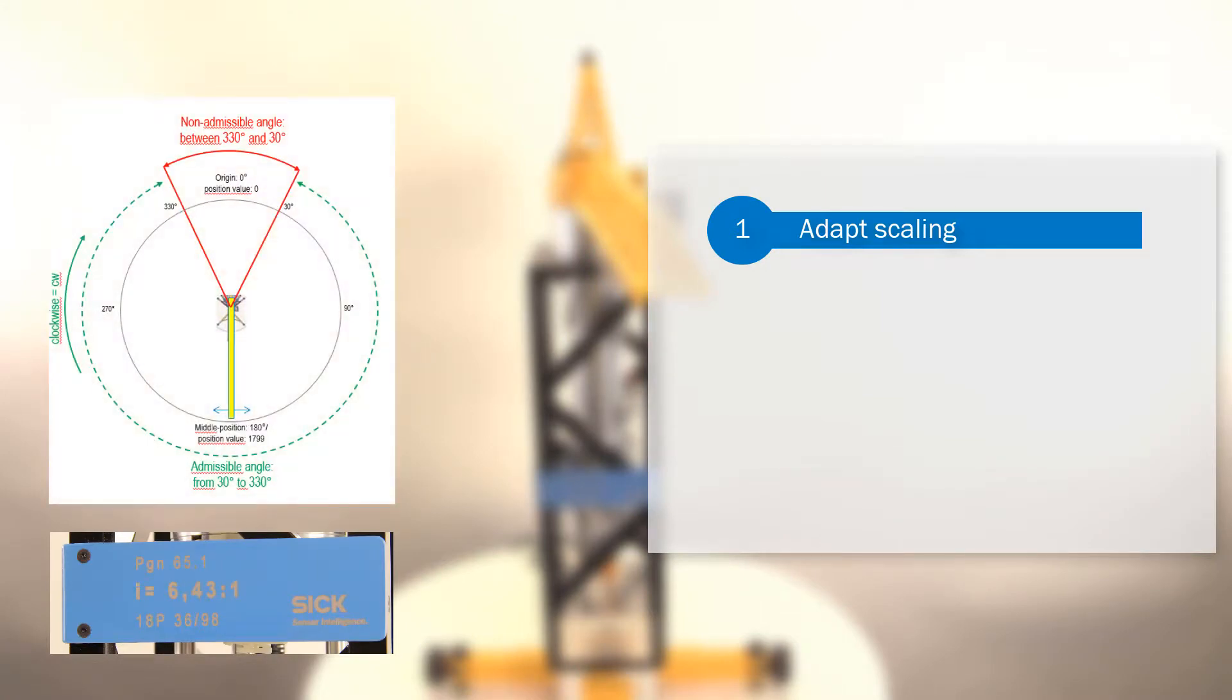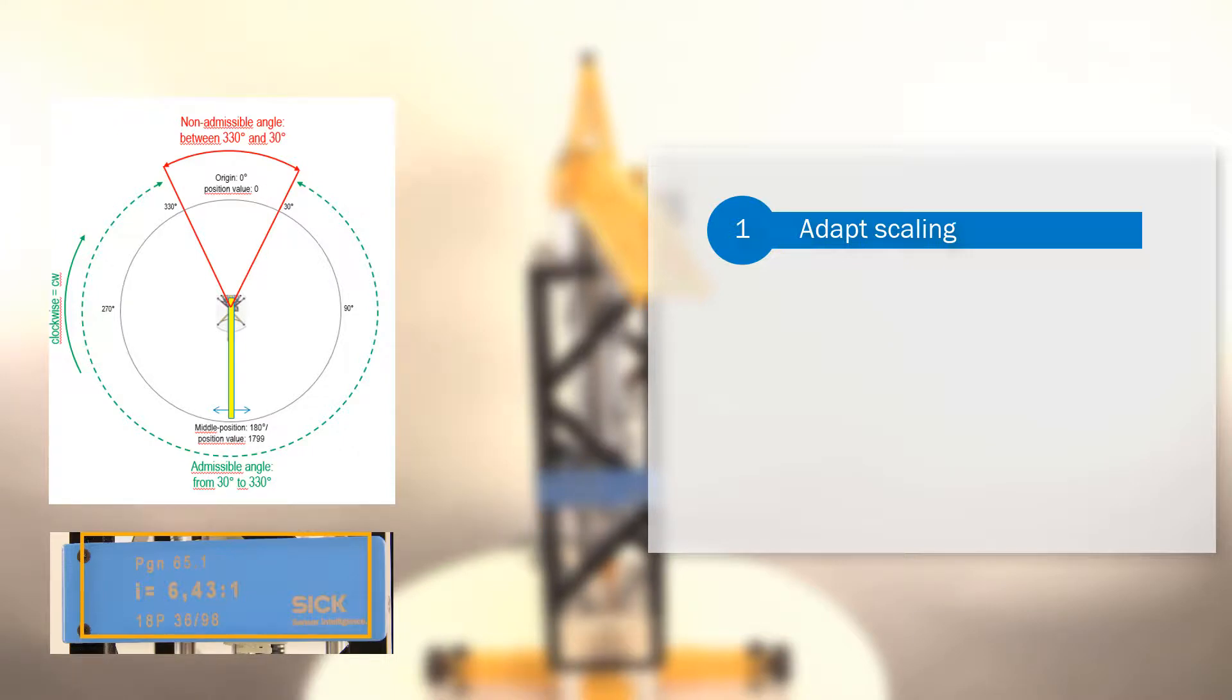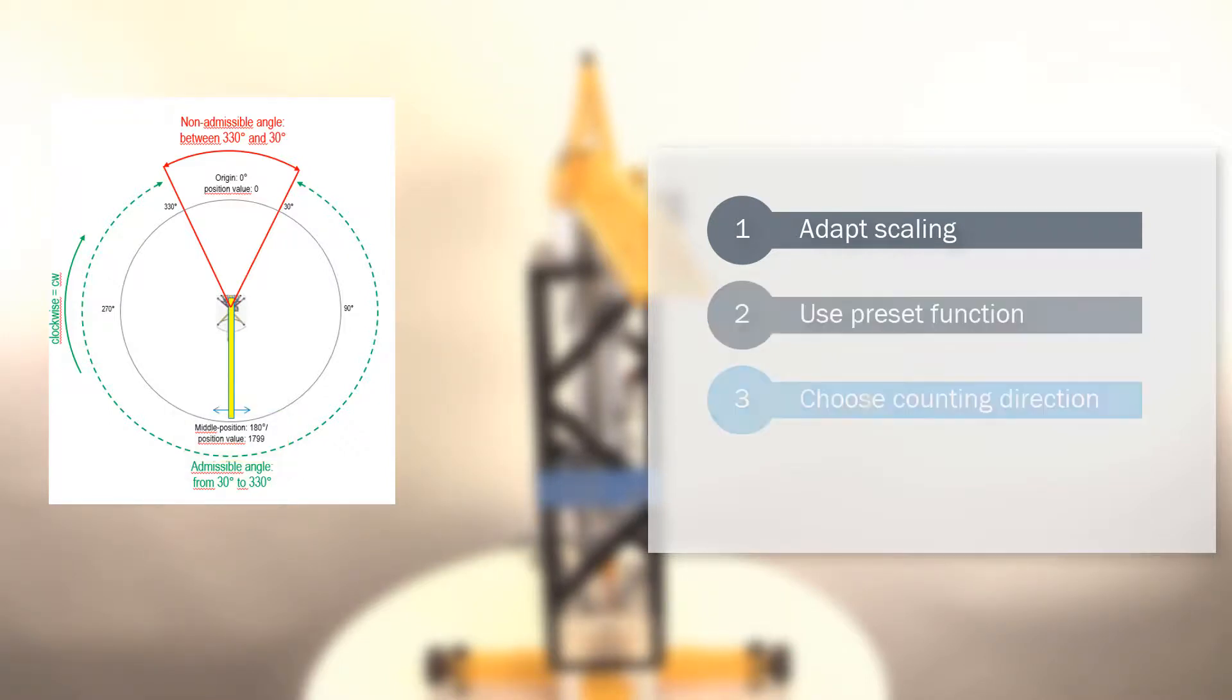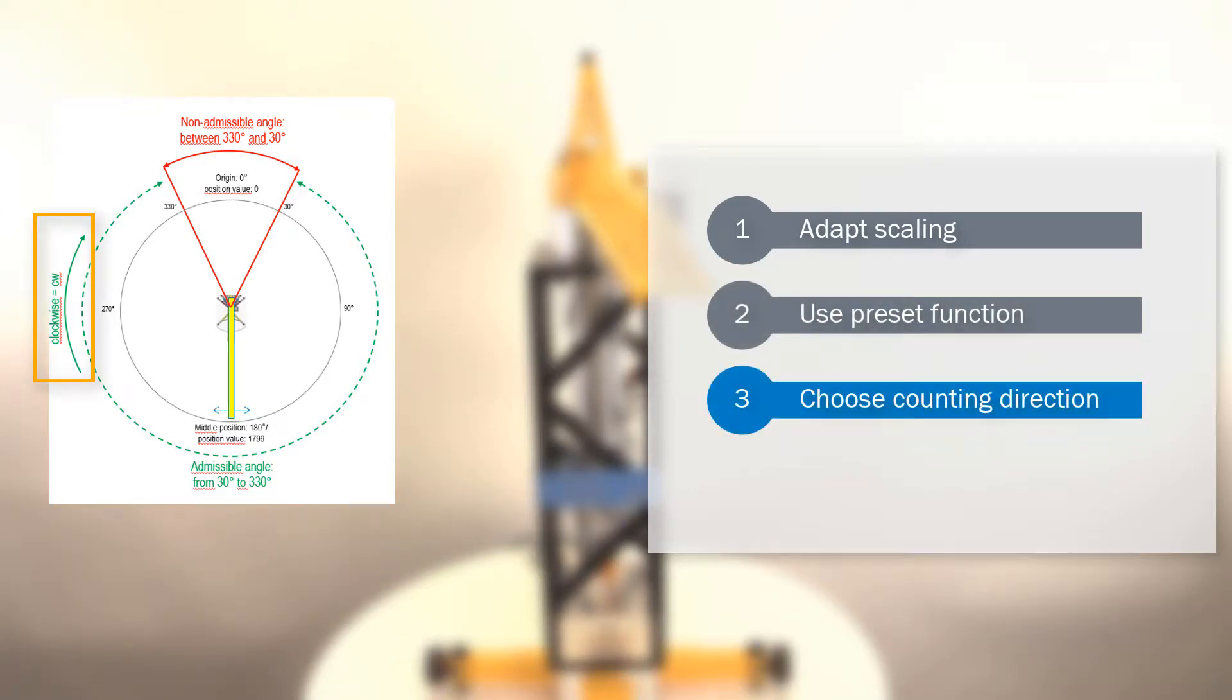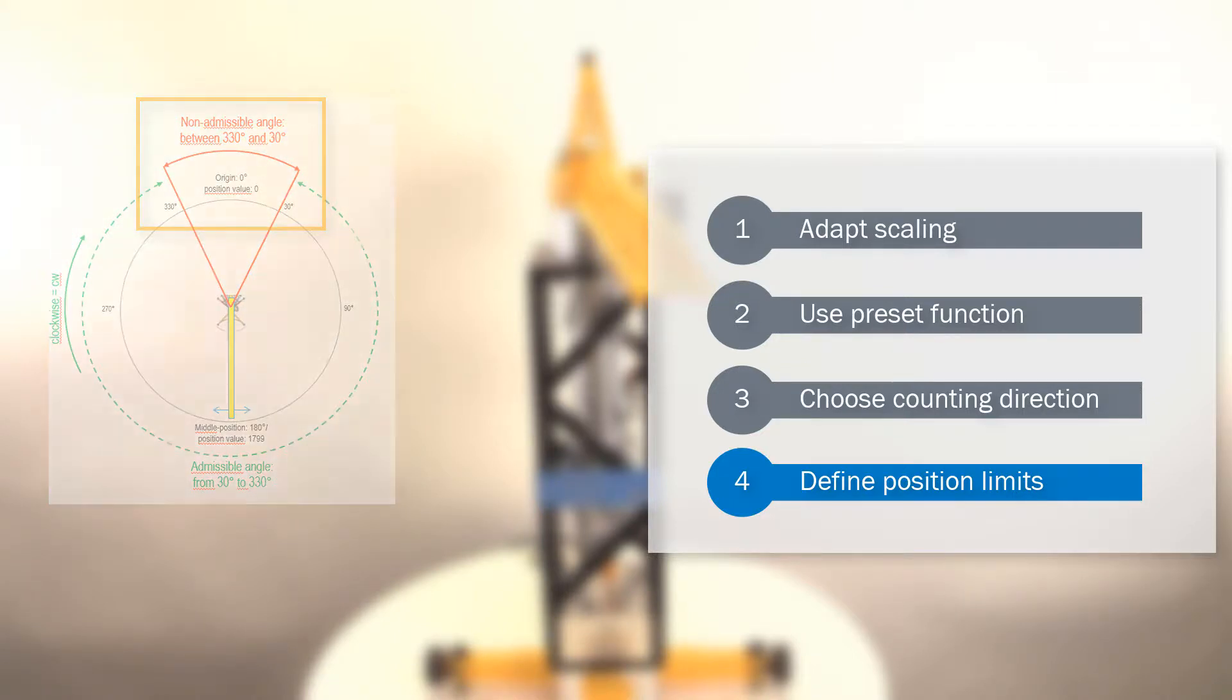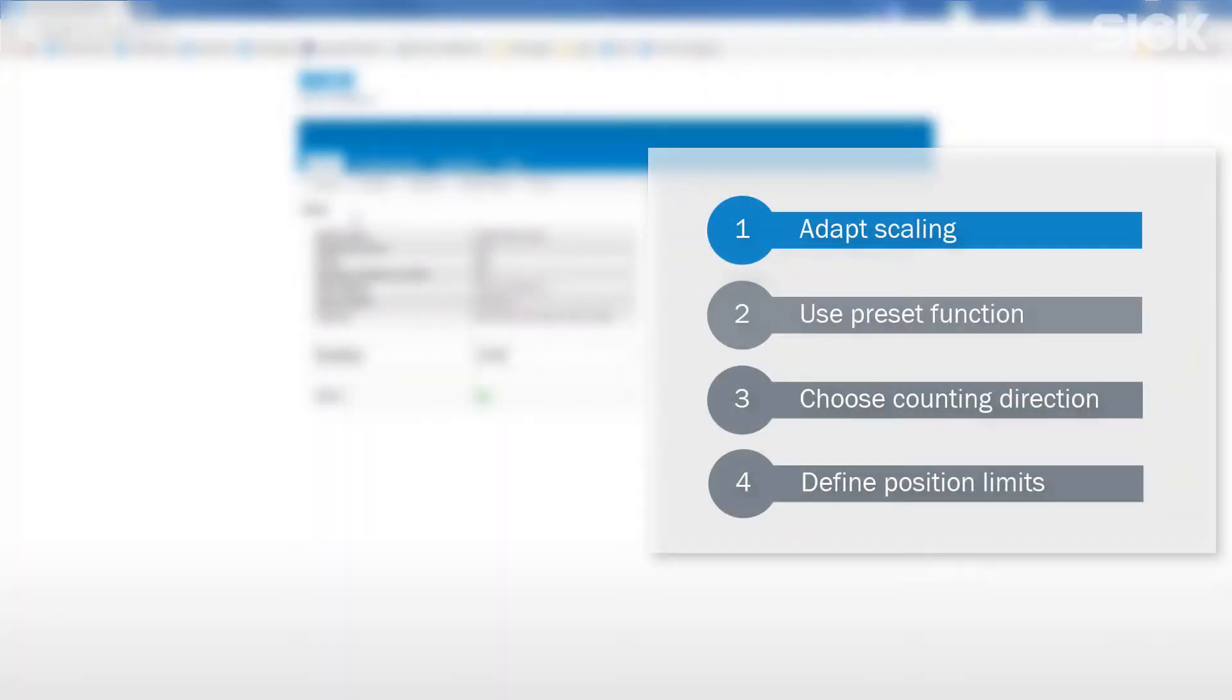1. Adapt the scaling of the encoder to the ratio of the application by using the round axis functionality. 2. Use the preset function in order to assign the desired position value to our starting position. 3. Choose the right counting direction for clockwise rotation. 4. Define two position limits for a status monitoring of the admissible rotation angle.